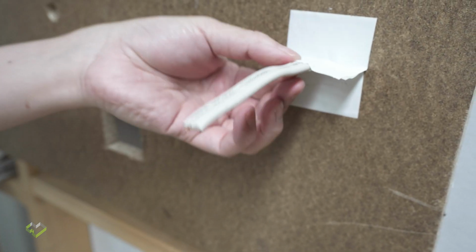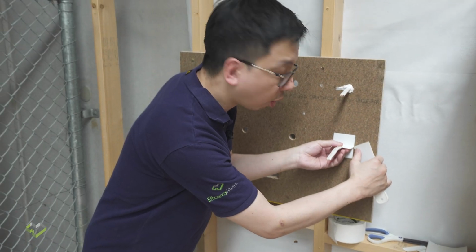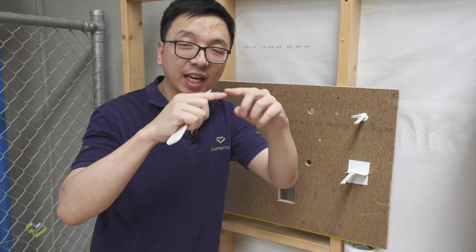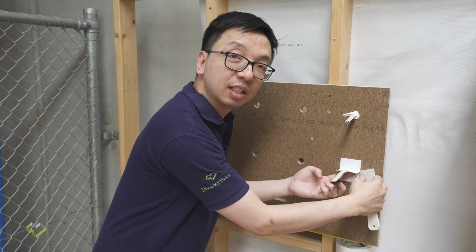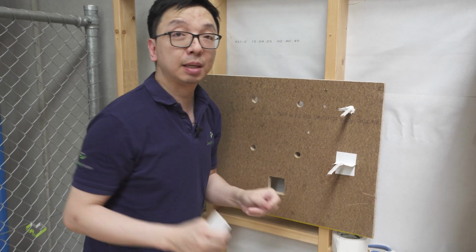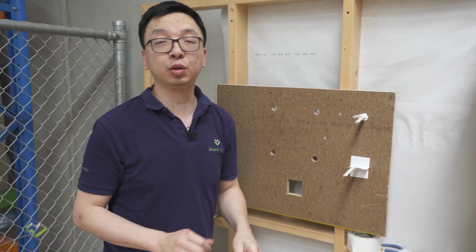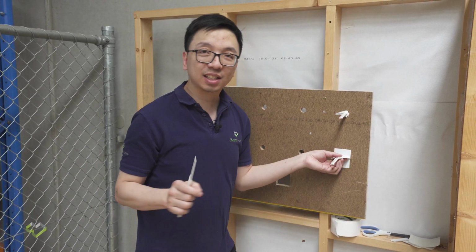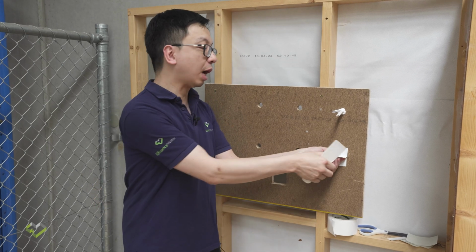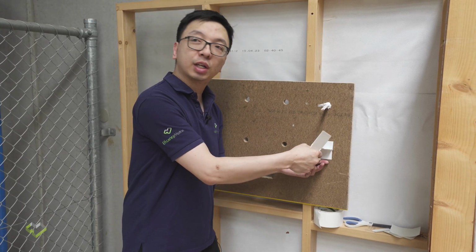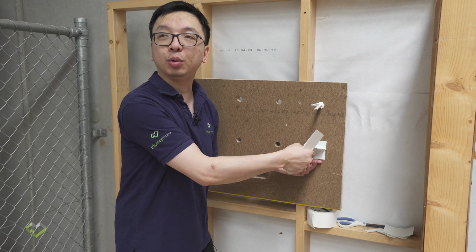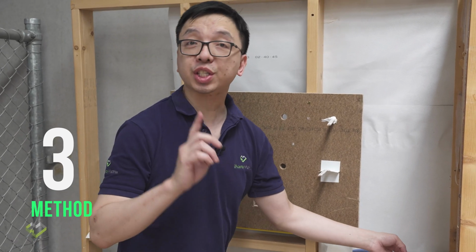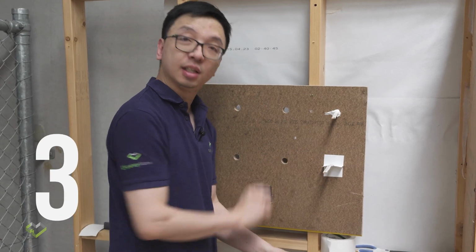Because the weakness of this method is the hole from the side where the two sheets of tape bond together to the surface. It's very easy to leave a small hole from the side. It may be small, but if you imagine you've got 100 cables passing through, they all add up. And the other not as preferable outcome from this method is you still can't push or pull the cable anymore once it's fixed in.